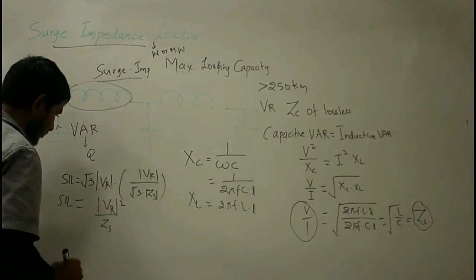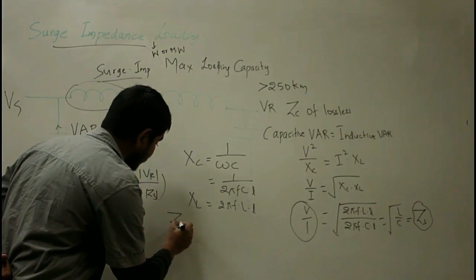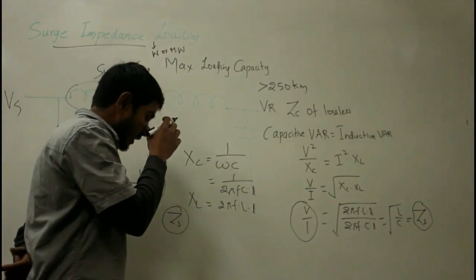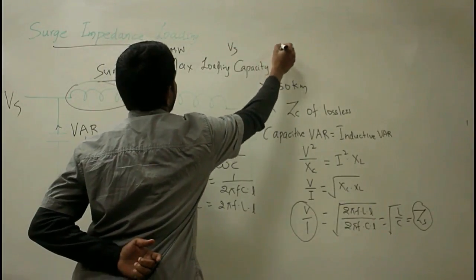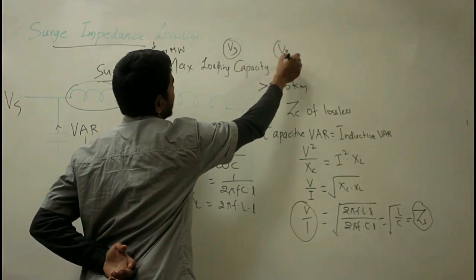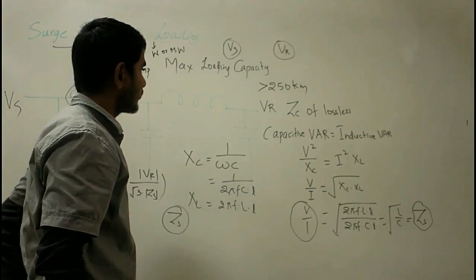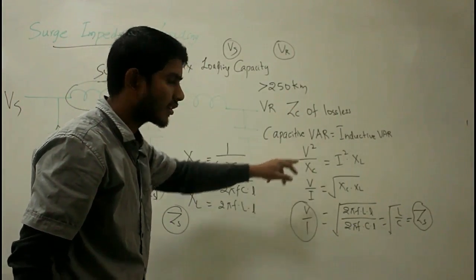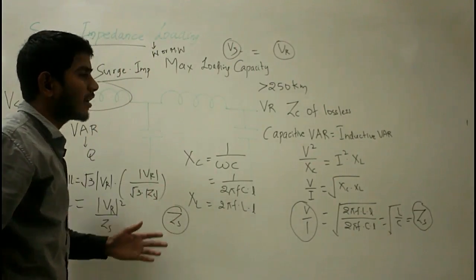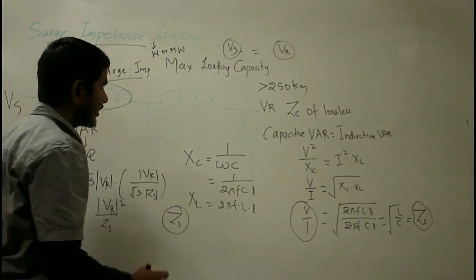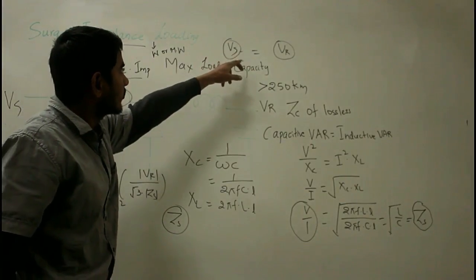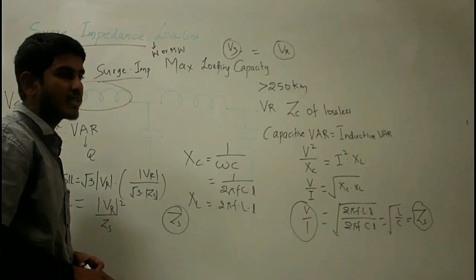When a line is terminated at the surge impedance, we have a lossless line. Normally, the sending end voltage Vs is greater than the receiving end voltage VR due to line losses. However, when we balance the two reactive powers and the line becomes lossless, Vs equals VR. This case is regarded as a flat voltage profile.